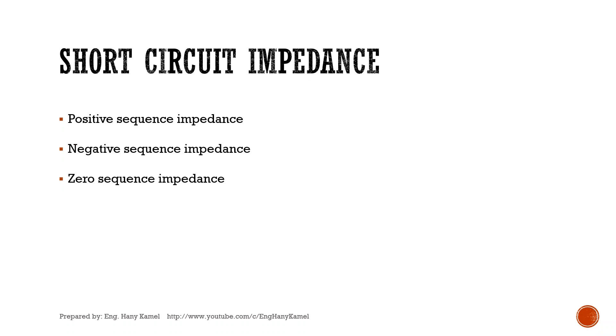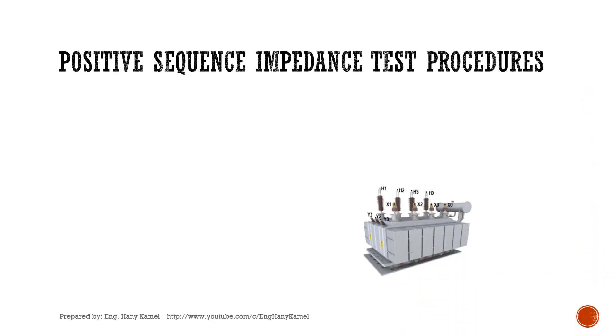As we know, short circuit impedance has three types: positive sequence impedance, negative sequence impedance — and in power transformers, negative sequence impedance is the same as positive sequence impedance, so no additional test is required — and then zero sequence impedance. We will start with the positive sequence impedance test.